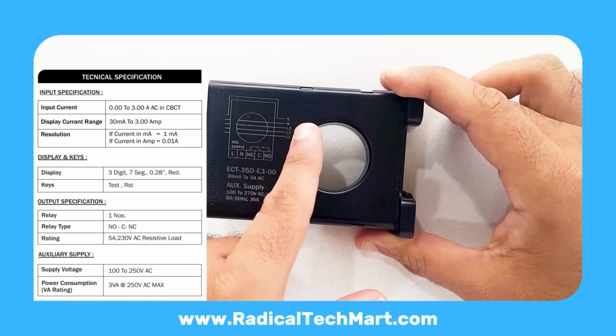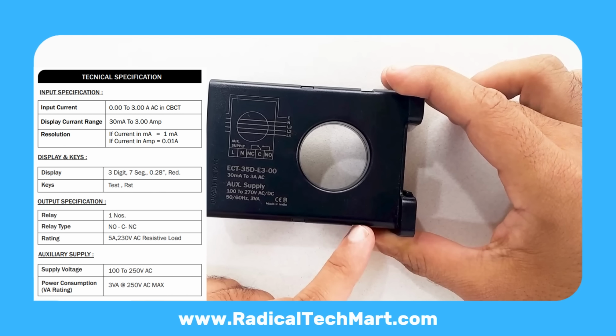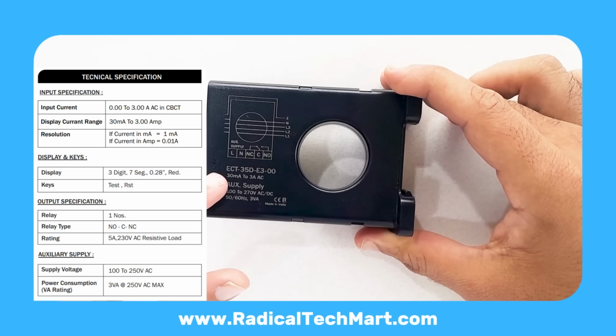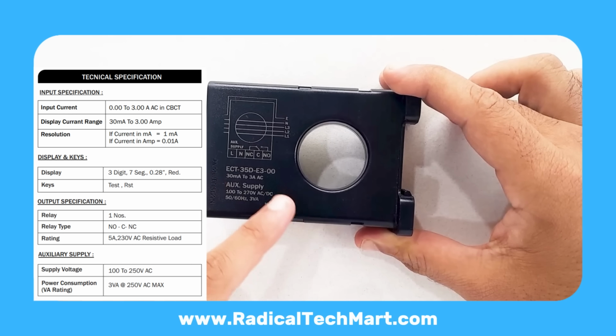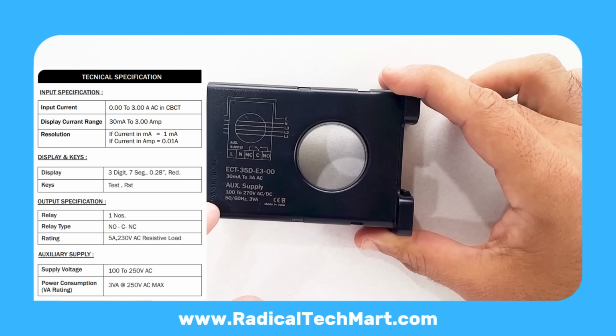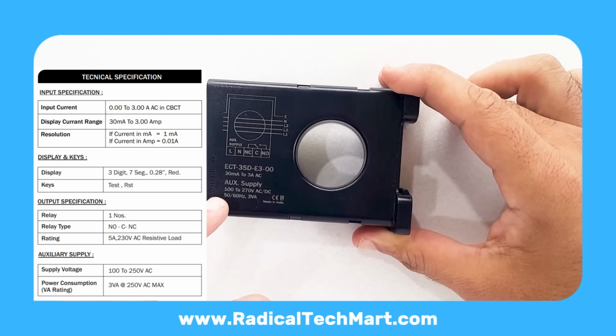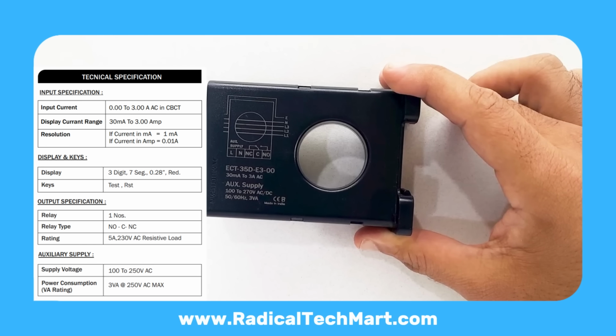The ECT-35D can measure and detect leakage current from 30 milliamperes up to 3 amperes, which covers most industrial protection needs. Its auxiliary supply range is wide, 100 to 270 volts AC or DC, which makes it suitable for both AC and DC control systems.